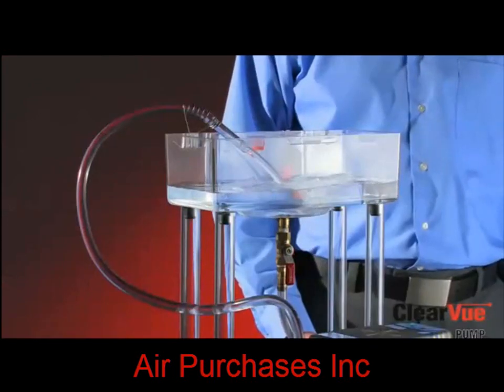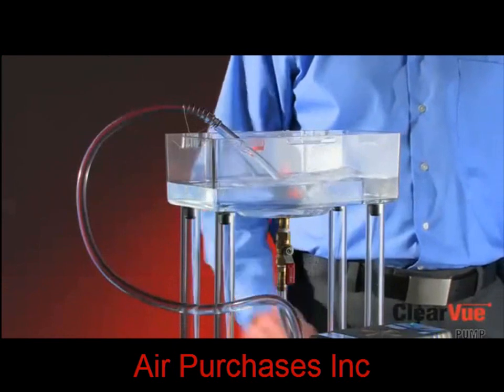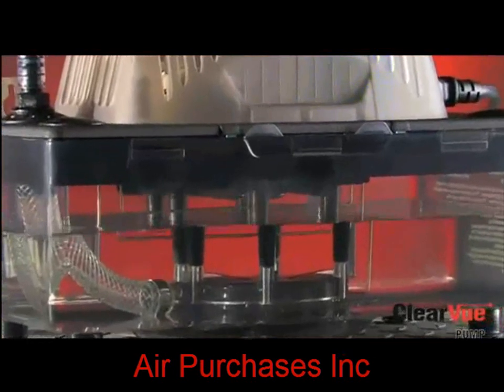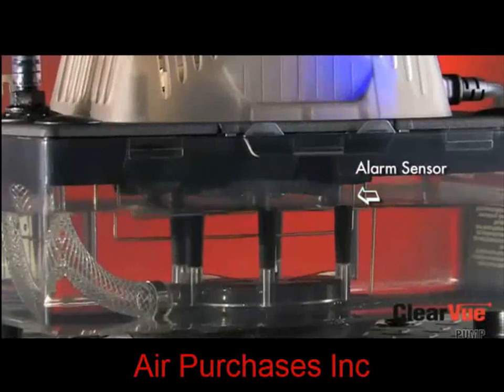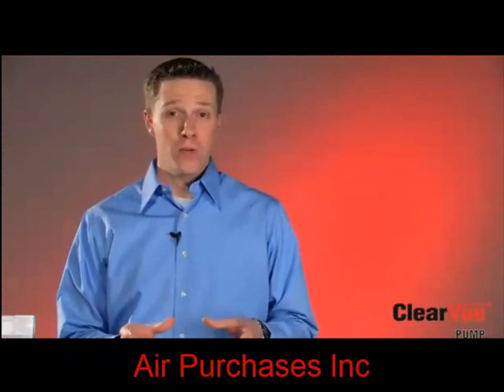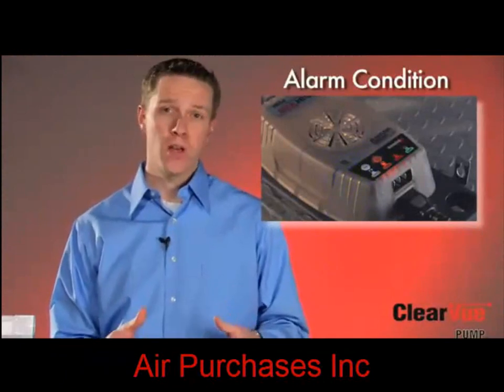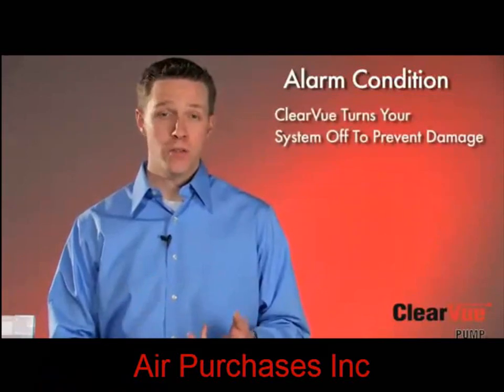If the water continues to rise to the high level sensor, ClearVue will go into an alarm condition. I'll block off the drain line here to simulate a clog or a kink. Since we've blocked the line, the water will continue to rise until it hits the high level alarm sensor. Now that it's hit the high level alarm sensor, it's engaged the alarm cycle. While ClearVue is in an alarm condition, a couple of key things are happening. First, ClearVue, if it's wired into your control circuit, has shut off the compressor, which will prevent an overflow condition or damage to its surroundings.